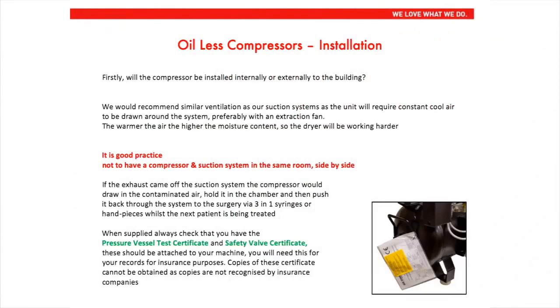Installation. Firstly, will the compressor be installed internally or externally to the building? We would recommend similar ventilation as our suction systems, as the unit will require constant cool air to be drawn around the system, preferably with an extraction fan. The warmer the air, the higher the moisture content, so the dryer will be working harder.